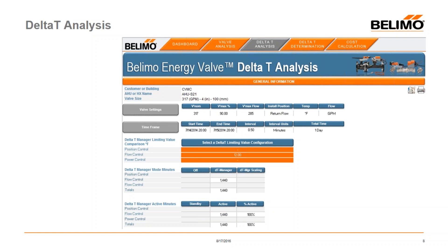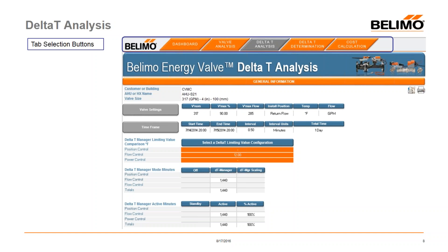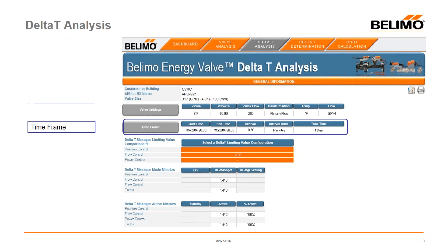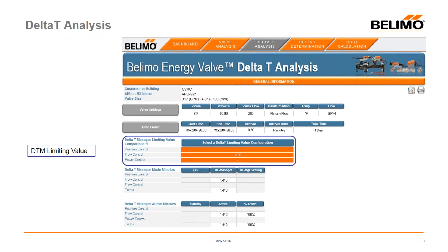The next tab is the Delta T Analysis tab — this is where it gets interesting, when we start really looking at what's going on in the system. We again start with the dashboard navigation and display customer, air handler, valve size, valve settings, and the time frame of data. Down below is the delta T limiting value by control mode, which shows based upon different delta T values what's going on in your system. A dropdown box lets you select values such as 10, 12, or 14 degrees to filter what's happening in the valve at each delta T limiting value — you can even compare them side by side.